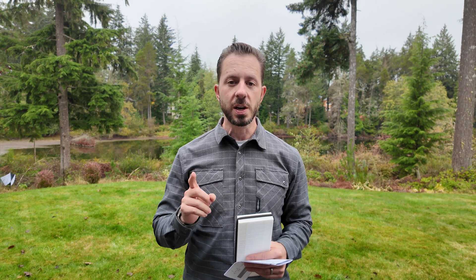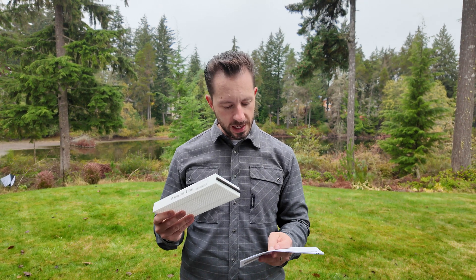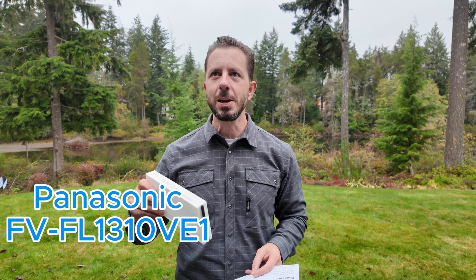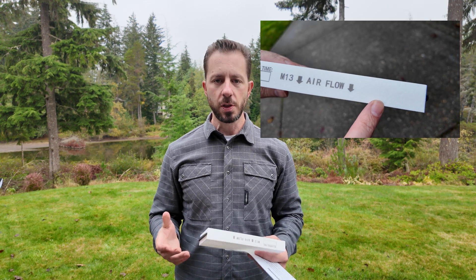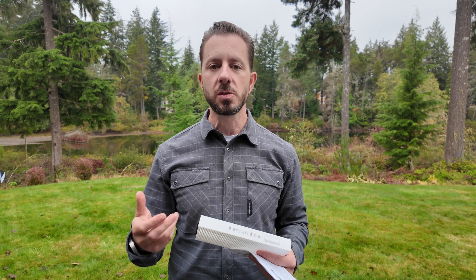There's one thing in particular that is very critical, and that comes down to the actual filter. This one here is the FV-FL1310VE1 — I'm going to put that up on the screen so you can see what that is. You might have noticed it has the number 13, that's for MERV 13. The unit that we're doing maintenance on is the Panasonic IntelliBalance 100, which comes standard with a MERV 8 filter. On the scale, the higher the MERV number, the more particulate matter it's going to be able to filter out.